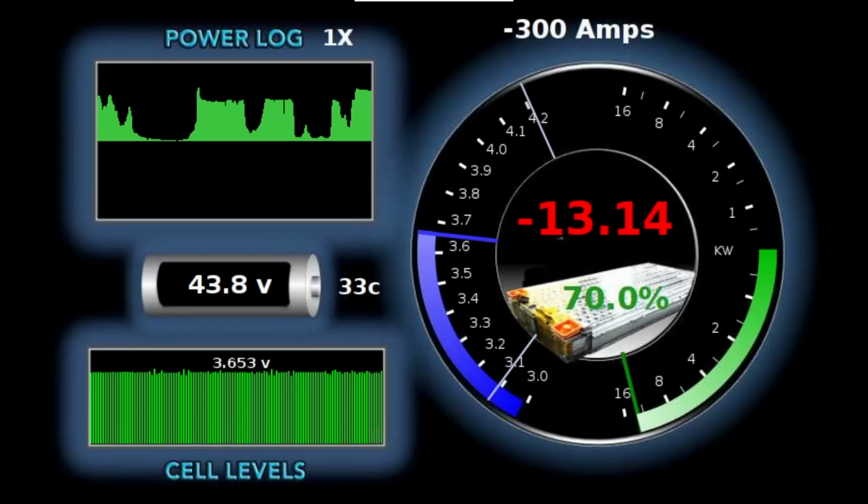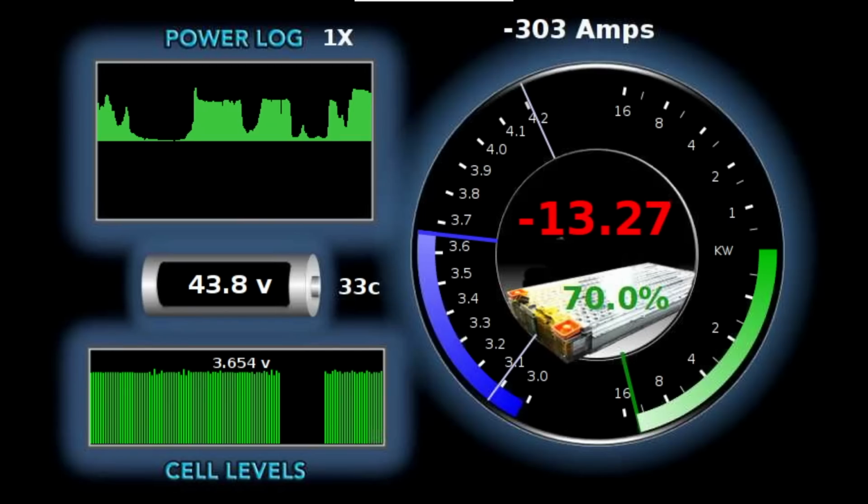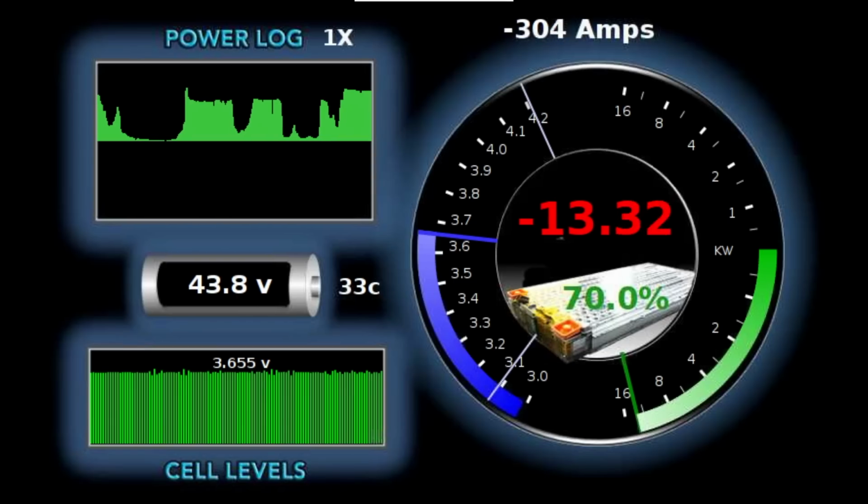It's supposed to be a 24 kilowatt array. At high noon, as they would say, we're getting 17 or 18, but that is the real world with solar, and like everything else, it's a little bit over advertised. It's still a pretty good amount of power. 17 kilowatts is pretty nice.